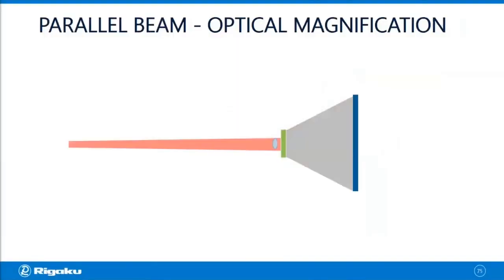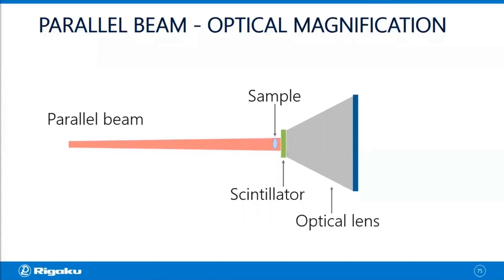For the parallel beam geometry, we use optical magnification. So you have a parallel beam, and you don't have a lot of divergence. Then you put the sample right up against a scintillator, which converts x-rays into visible light so that you can use optical lenses to do the magnification.